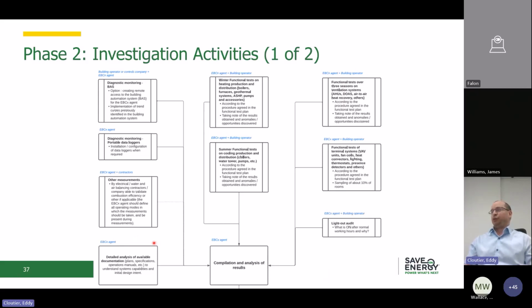So what do we do in the investigation phase? Basically, it's a lot about functional testing, on different types of systems that we need to test. The first step is to set up diagnostic monitoring on the BAS system at the control station. It's always a good option to create remote access to the BAS system, as it highly facilitates the work of the EBCx agent. But if that's not possible, for security or other reasons, it's also possible to do this work on site. Basically, we implement trend curves in the BAS system to know how the systems are operating during a week, a day, during the night, etc.